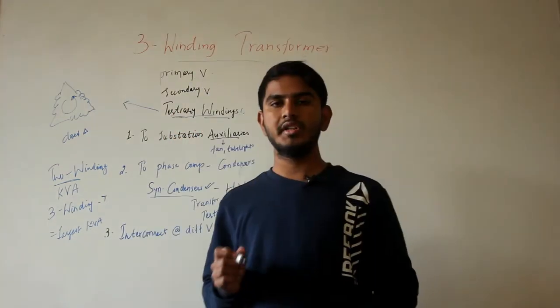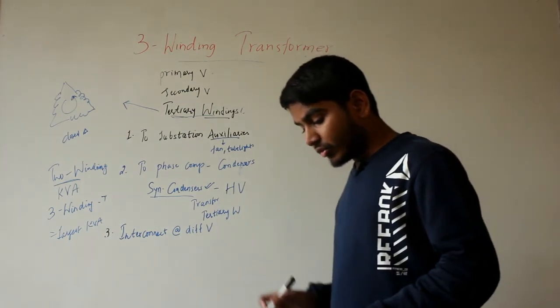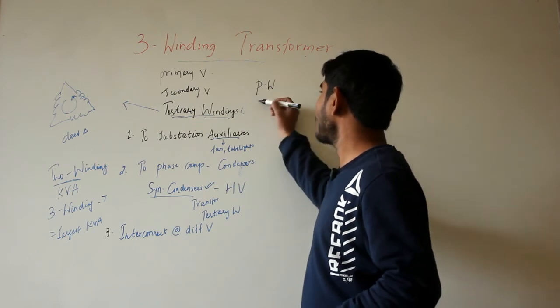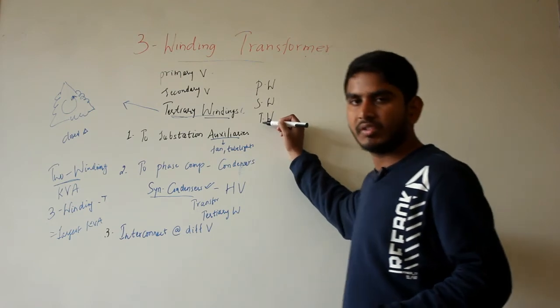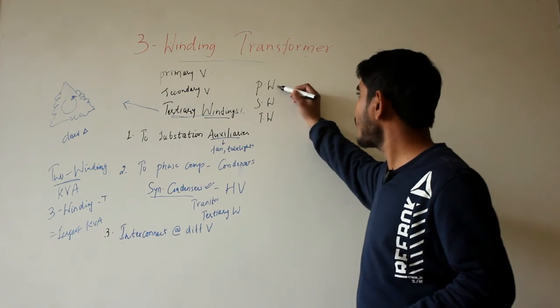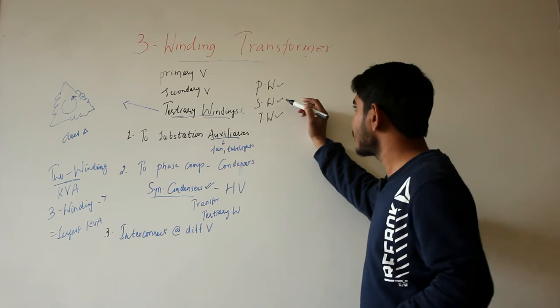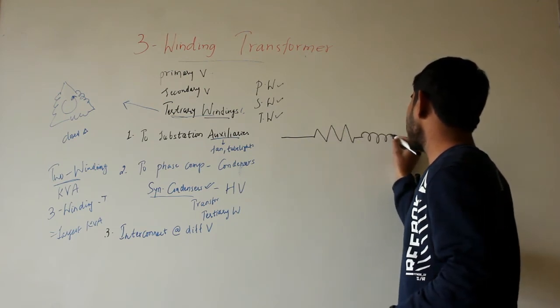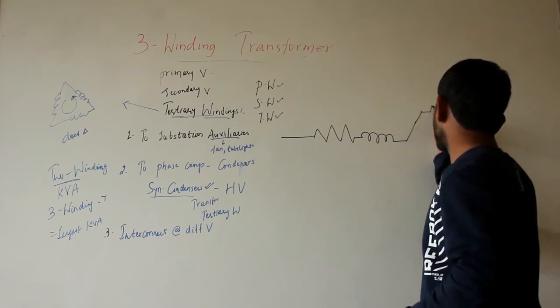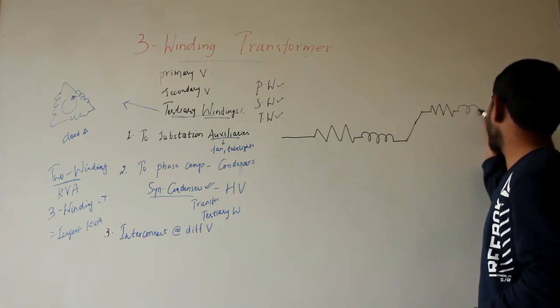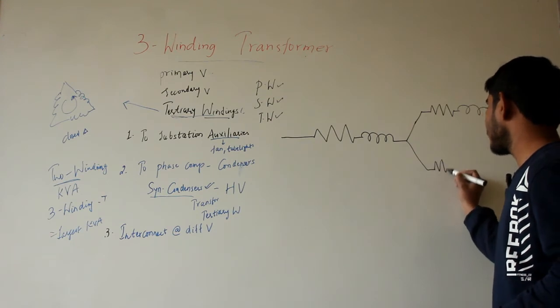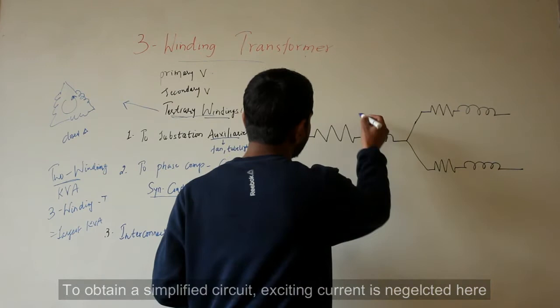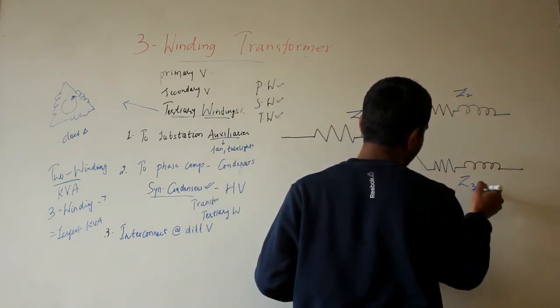The equivalent circuit of a three-winding transformer can be drawn with each winding represented by its own resistance and leakage reactance — giving impedances Z1 for the primary, Z2 for the secondary, and Z3 for the tertiary. The three terminals are connected to three external circuits: terminal 1 is connected to the supply, while terminals 2 and 3 are connected to the load. These impedances, all referred to a common base, can be found by conducting three short-circuit tests.